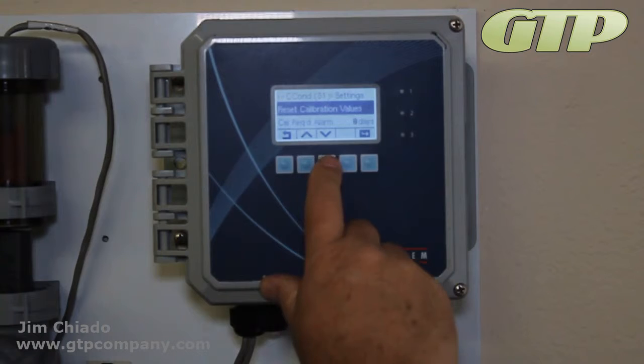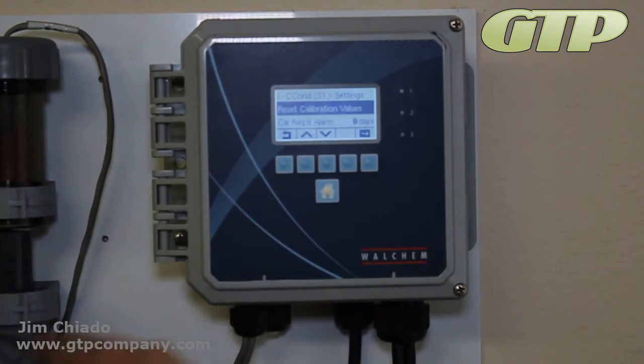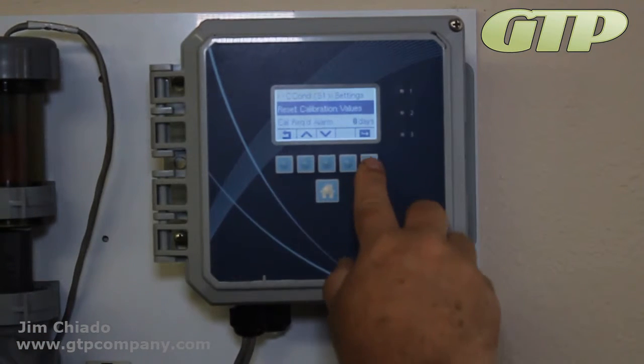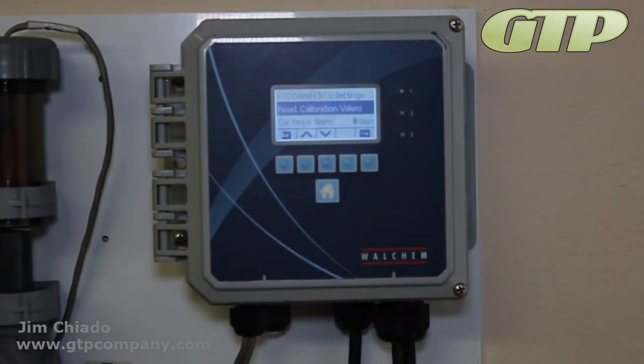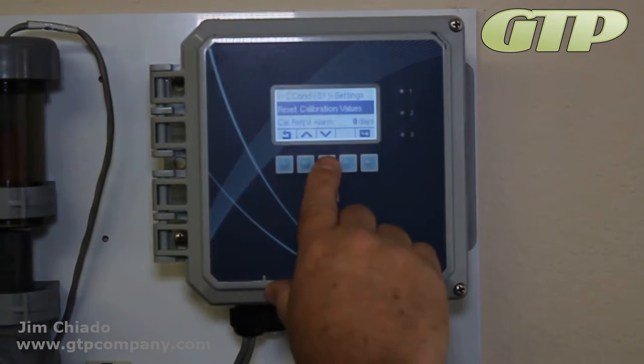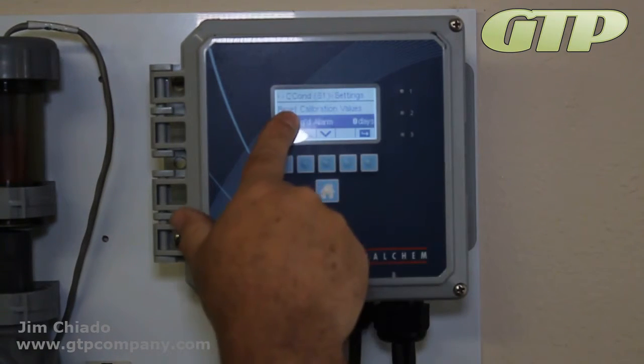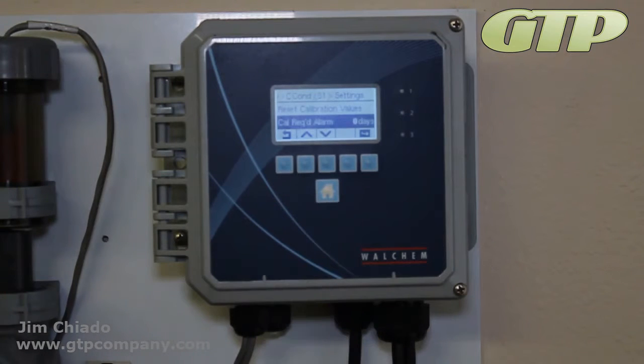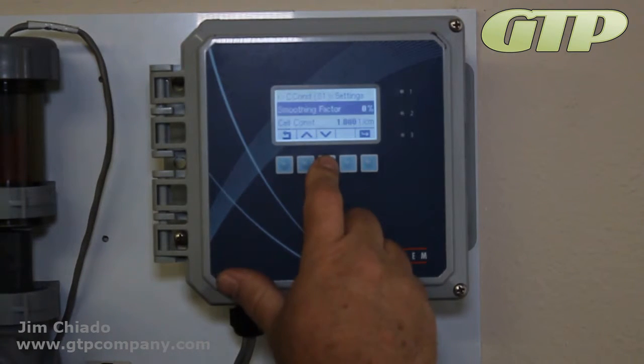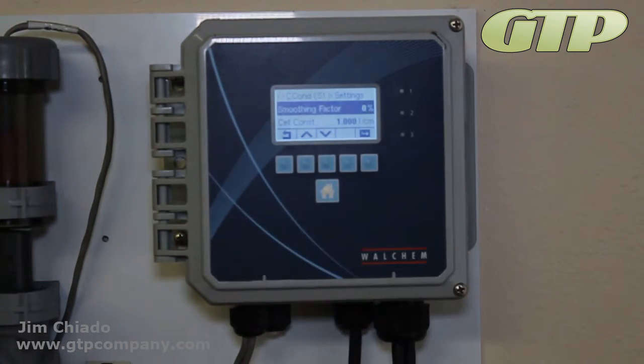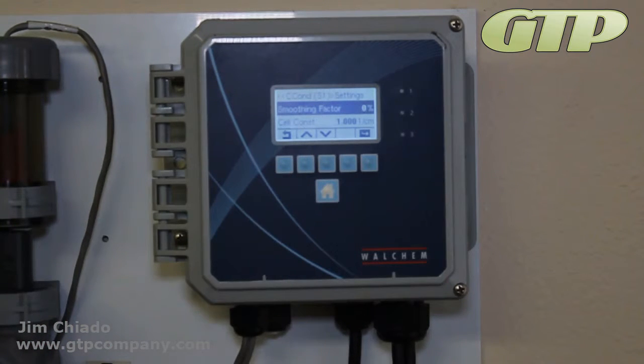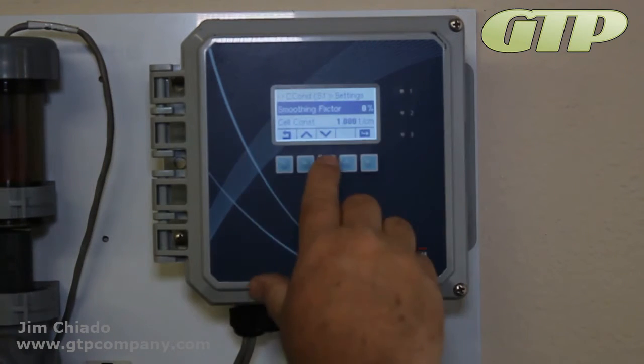Reset calibration values. Switching sensors out every once in a while, resetting the calibration does make sense. I want to reset them, start with a fresh, clean slate. Cal required: you can make the machine tell you that every 30 days you want to run a calibration. Not really necessary. Most of the guys that work on this will come out every 30 days, and typically they do a calibration every time. Smoothing factor is to stop the reading from jumping. As we walk out here, we know there's a lot of flow going through here, and the reading jumps up and down.